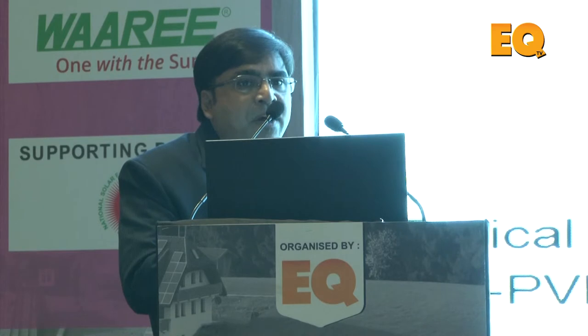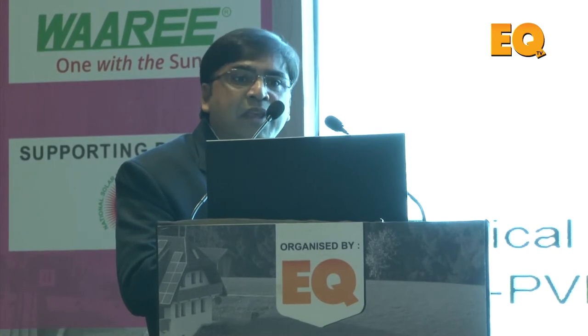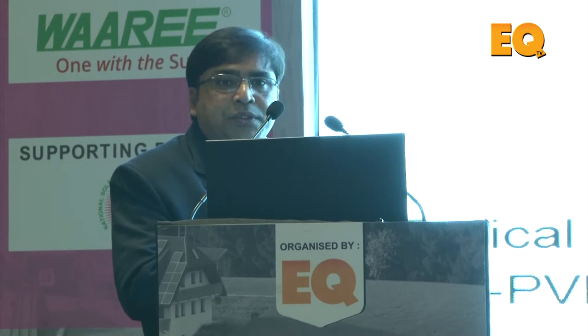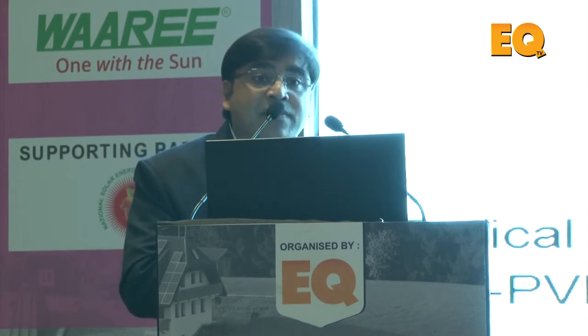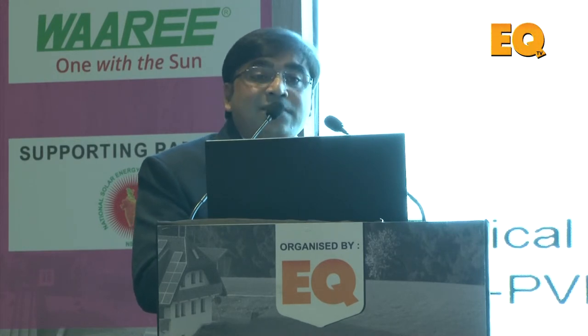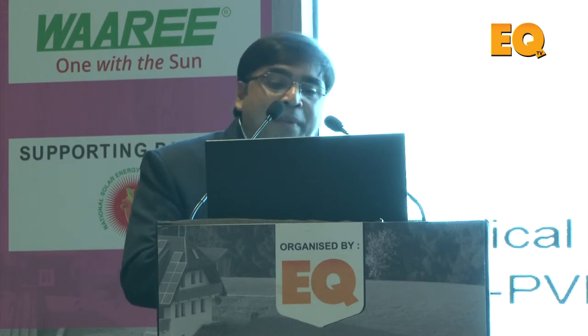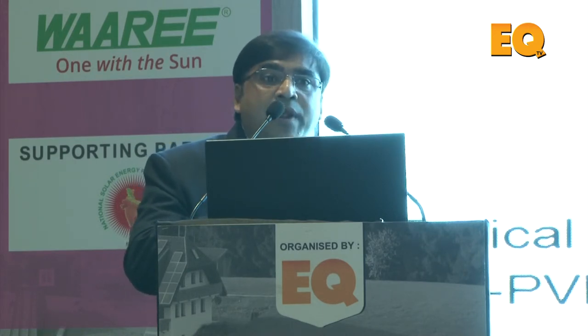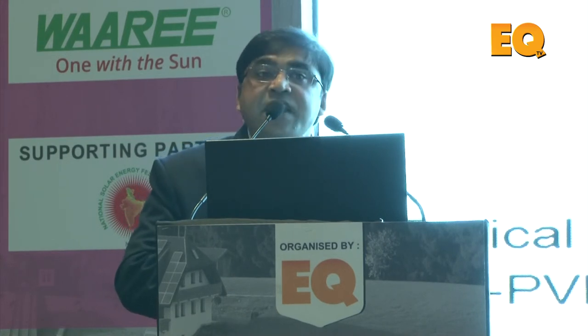The rest, 20%, is because of the EVA. In most cases, EVA is there. EVA gets yellow, and yellowing of the EVA contributes around 10%. Another is corrosion, which again comes from the EVA. Apart from that, there are other kinds of problems: PID, snail trails, and junction box failure. But in the standard, this is one of the things. I can straight away tell you, I am completely against the EVA.